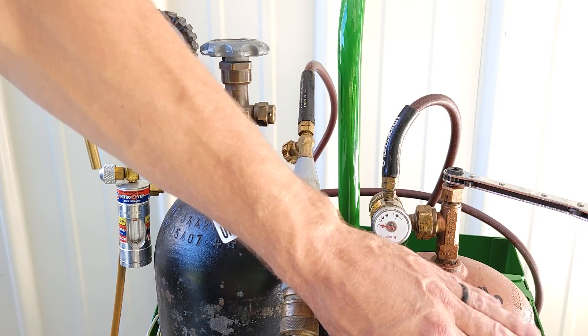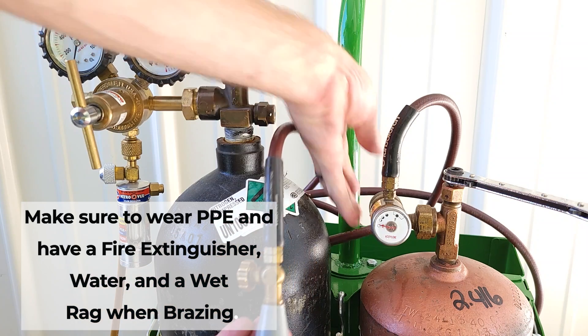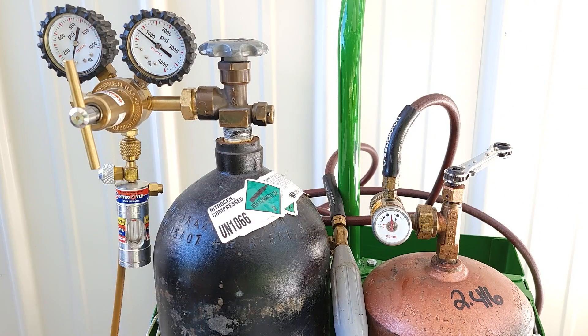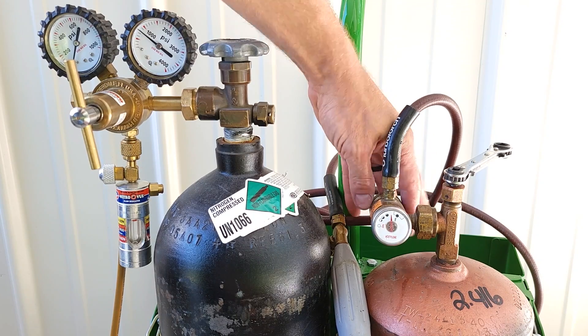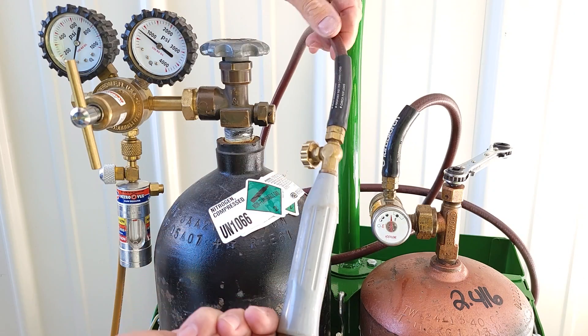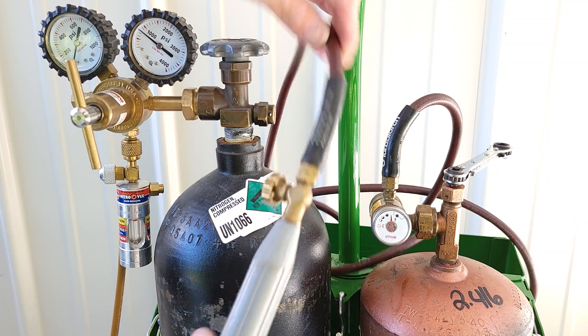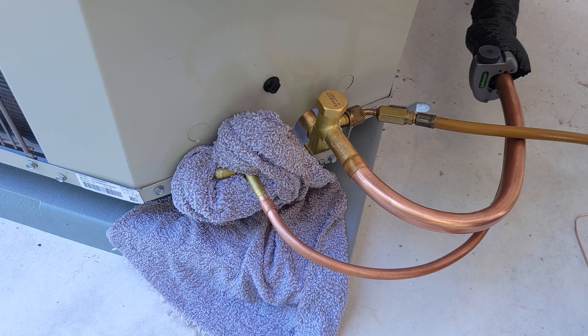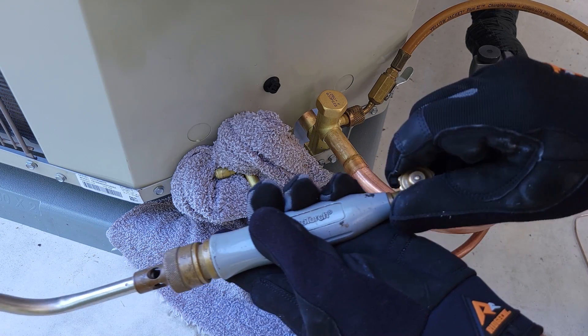Over here with our air acetylene tank, we have our regulator attached. We're reading empty. This is closed and this is backed out. The first thing we're going to do is open up the tank and leave our wrench on there, and then we can turn this in clockwise and now we have acetylene. So now we're ready to go. Before we start brazing, I'm going to turn this down and then we can light our torch. We have it all wrapped up with our wet rag. We can light our torch.